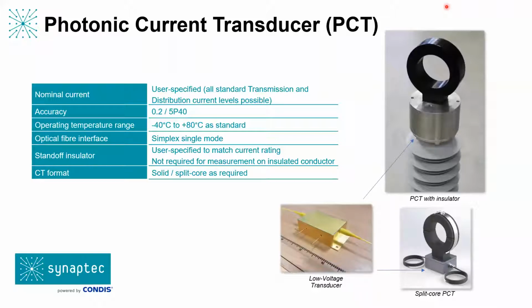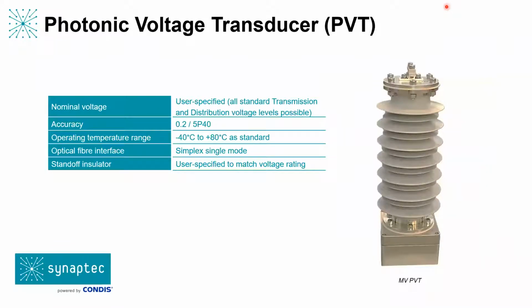We can deploy on secondary or primary systems, and we can deploy solid core or split core, depending on the environment, whatever makes the installation easiest. For voltage, we have also launched the first commercial optical voltage sensor that's really optical and is not performing some ADC at that point of measurement. Again, we have a huge dynamic range and also temperature range. Each of our optical voltage sensors is inherently dual metering and protection class. And so we can deploy that over virtually any voltage level, from low voltage all the way up to the highest transmission level. And we partner with Condis in Switzerland, who are manufacturing experts of high voltage devices, in order to go up to those highest voltage ranges.